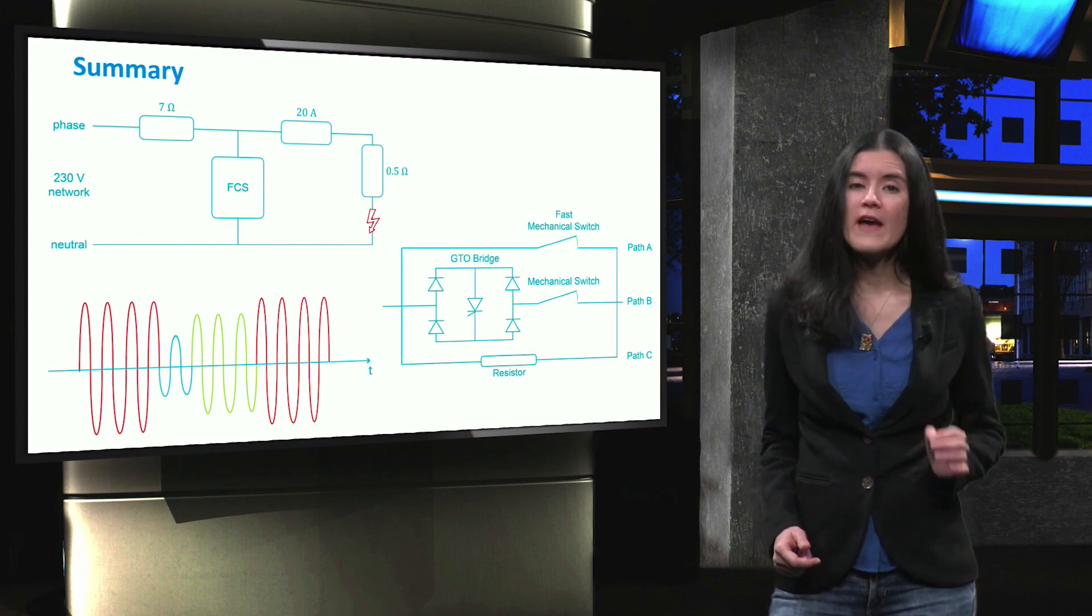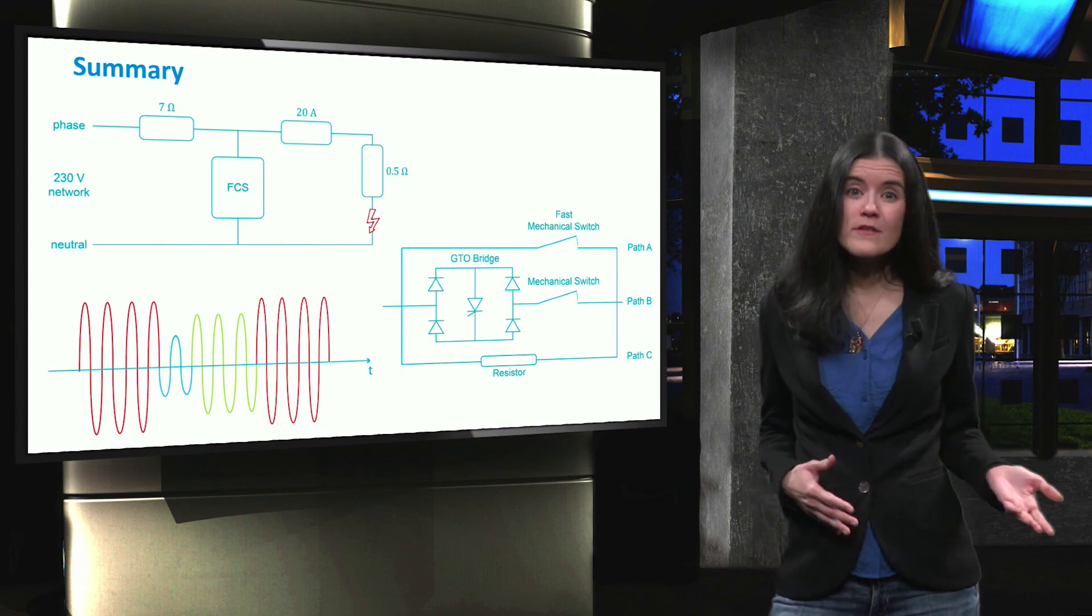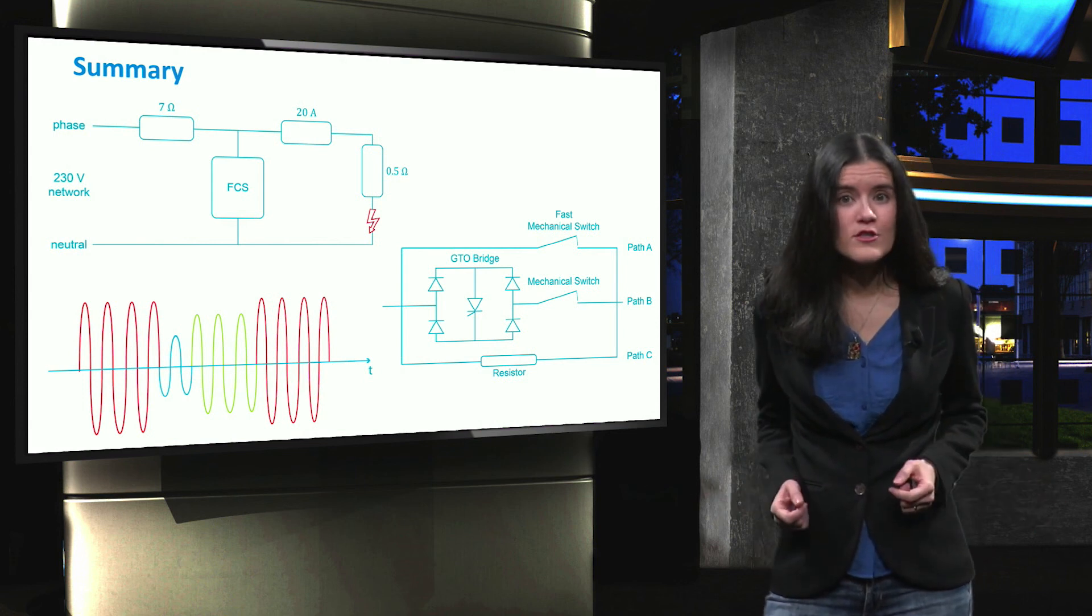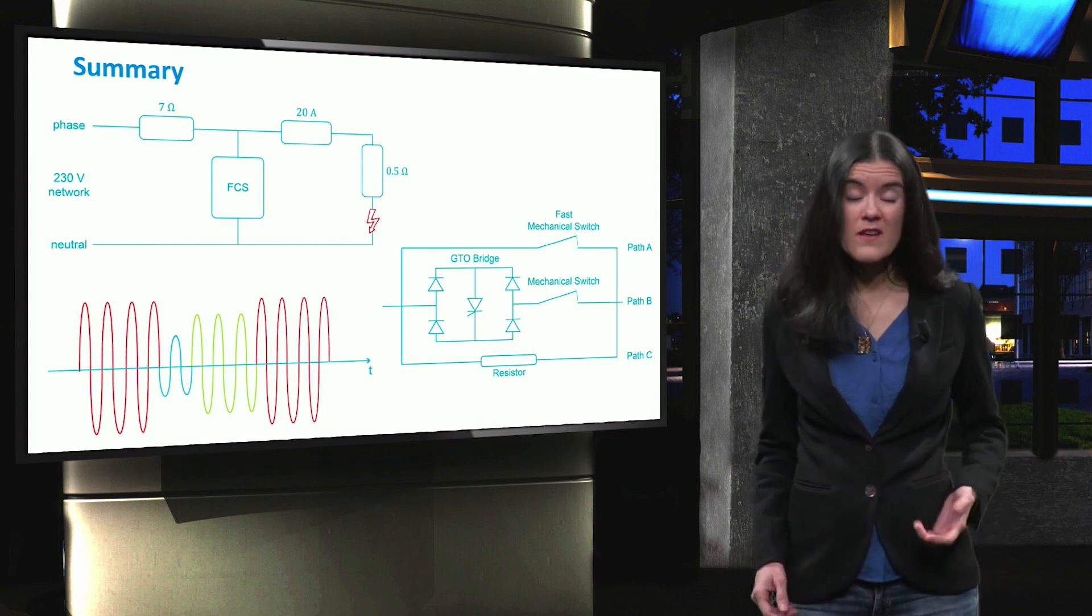Passive solutions have the advantage of always being operational, but generate losses due to their high impedance, whereas active solutions are more efficient and act only during faults. They need to be replaced after a fault.